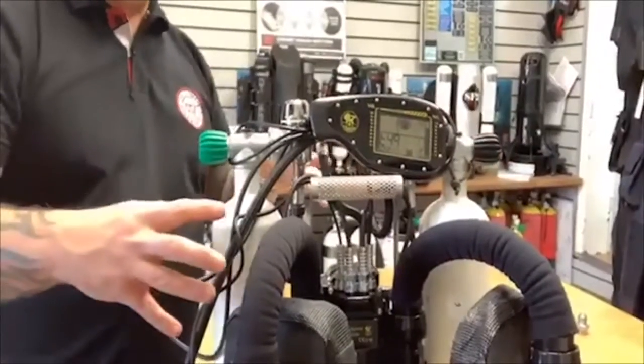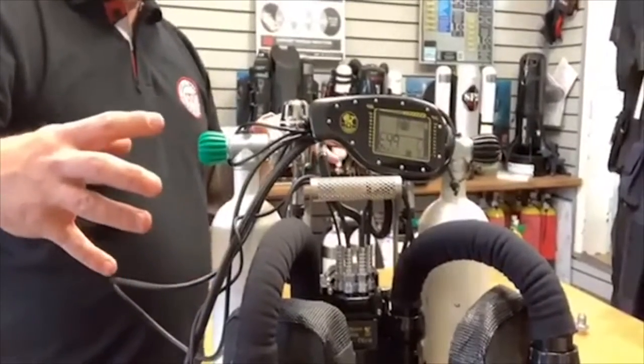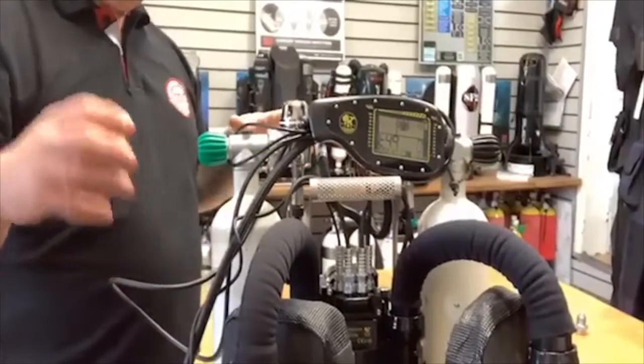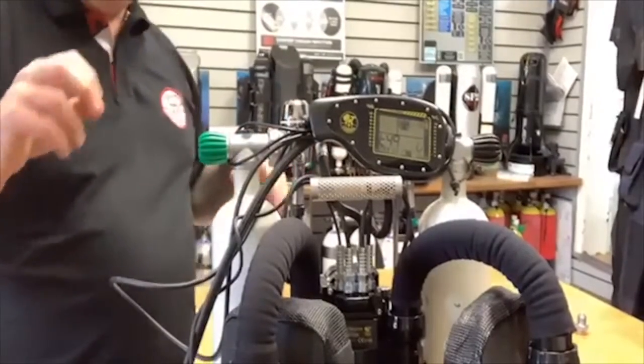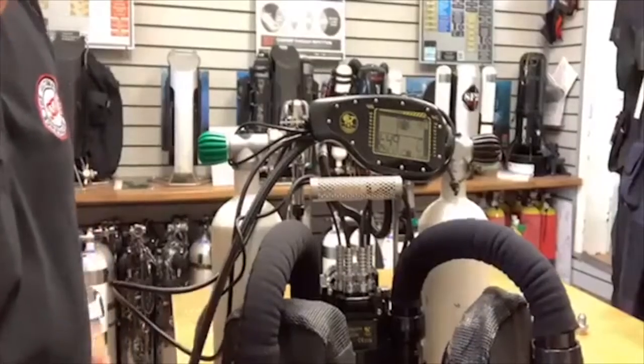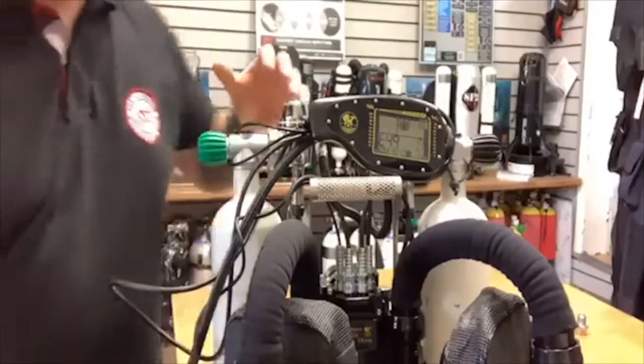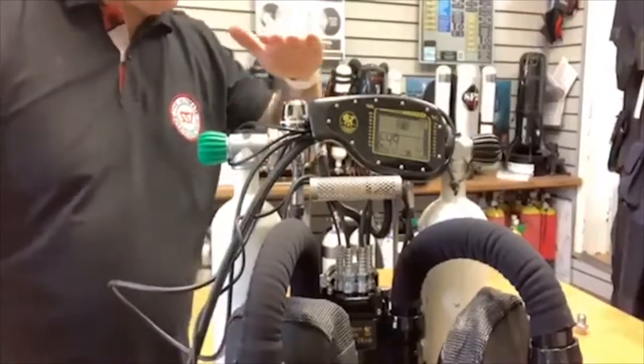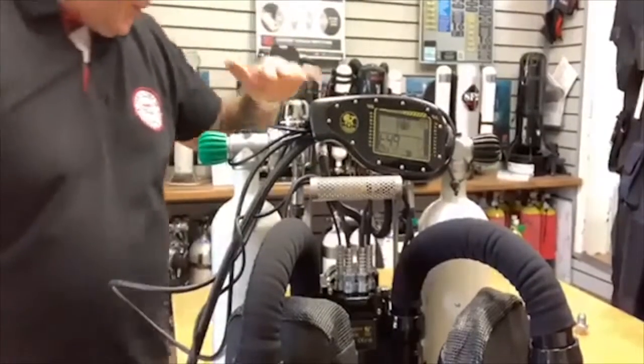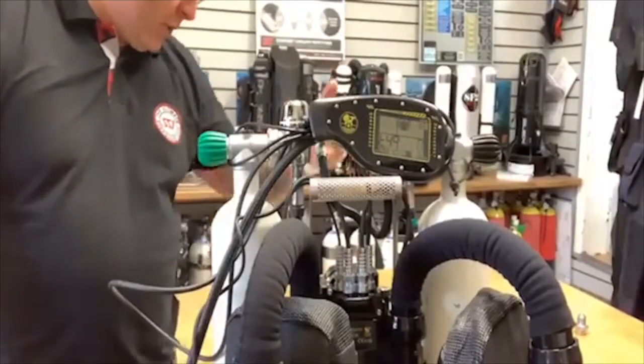Now you can see the machine injecting. It's injecting and blowing itself up to that low pressure, and then it's going to stop the two solenoids. When it's stopped, it's going to check and level off. If that pressure remains constant, we know for sure that our solenoids aren't leaking.